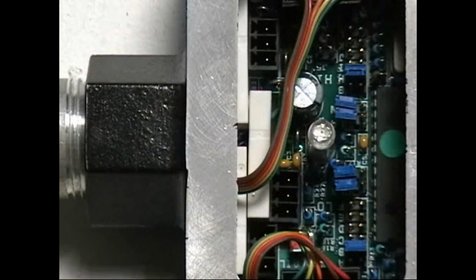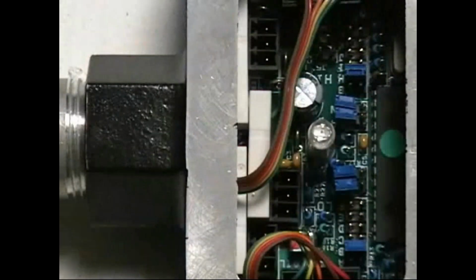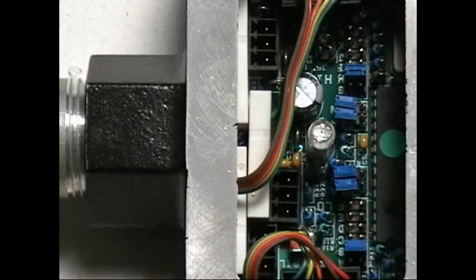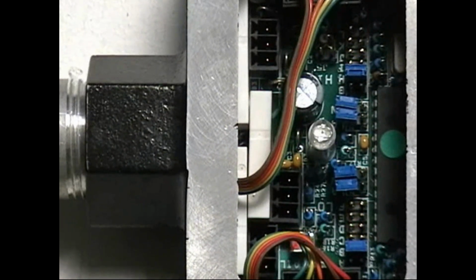The last jumper on board is dedicated to 125 ohm termination resistance. It is necessary to terminate the RS-485 data lines only if transmission data is corrupted or intermittent. These resistors are placed on the extreme ends of the data lines. Again, for more detail, please refer to the manual.